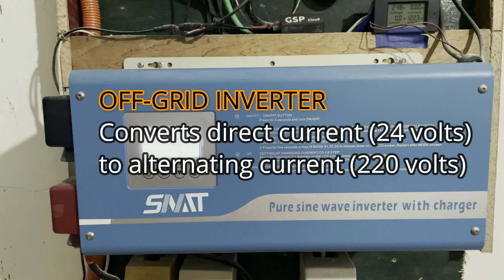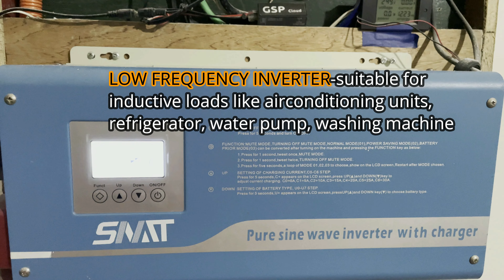This massive device is a 6 kilowatt, 24 volt low frequency pure sine wave inverter that converts the direct current from the battery bank to an alternating current that is similar to the power supplied by our power distribution utility. It can absorb power up to 6,000 watts, but we're not overstressing this device. It also has a built-in transfer switch, but we're using the standalone ATS since it only transfers the connection from the mains power to solar when the battery is almost full, and transfers the power back to the DU even when the battery is still at 70%.